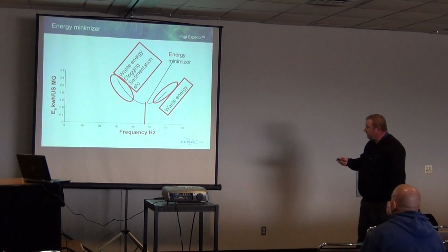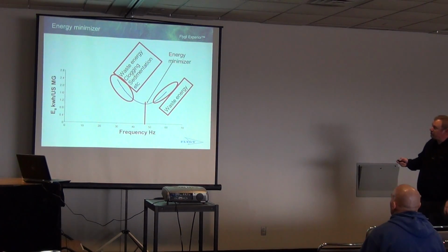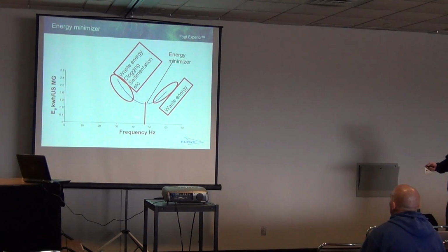This is a good point to make too: when you get too slow, you start to clog and get sedimentation. When you get down to a point in that system curve where you slow down too much, you can lose that scouring velocity. And when you get to the right, over here, you're wasting energy. So all of our on-off stations, where do they run? They run here all the time. We're turning them on and off at 60 hertz all the time. If we were to optimize the energy with these units and bring it down to 48, we're going to have it in that nice spot.